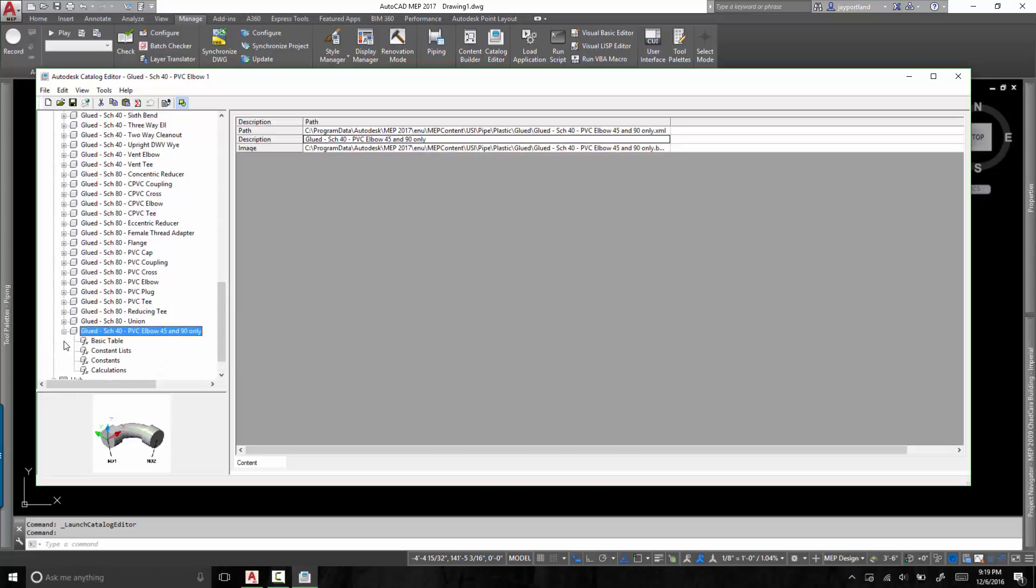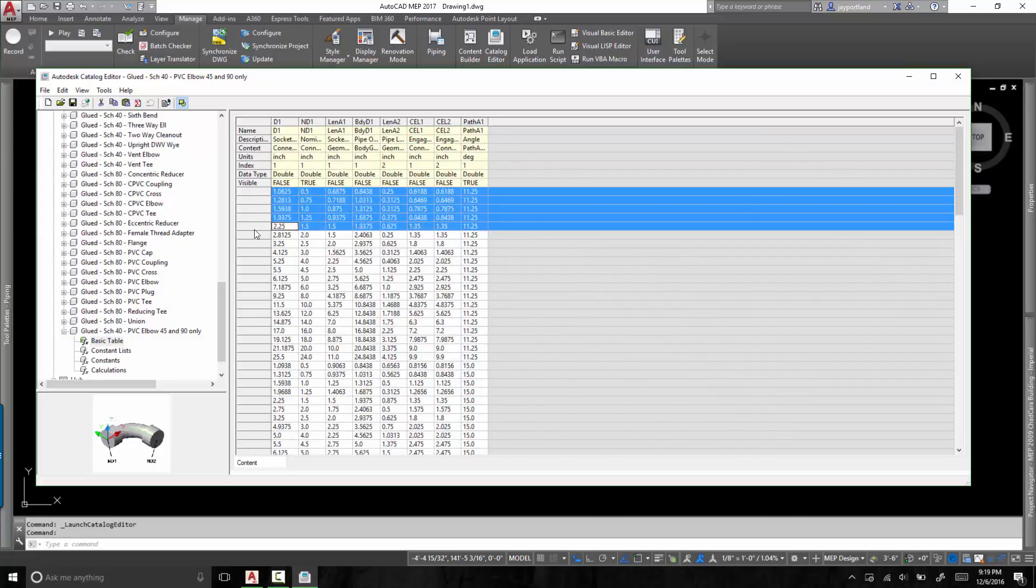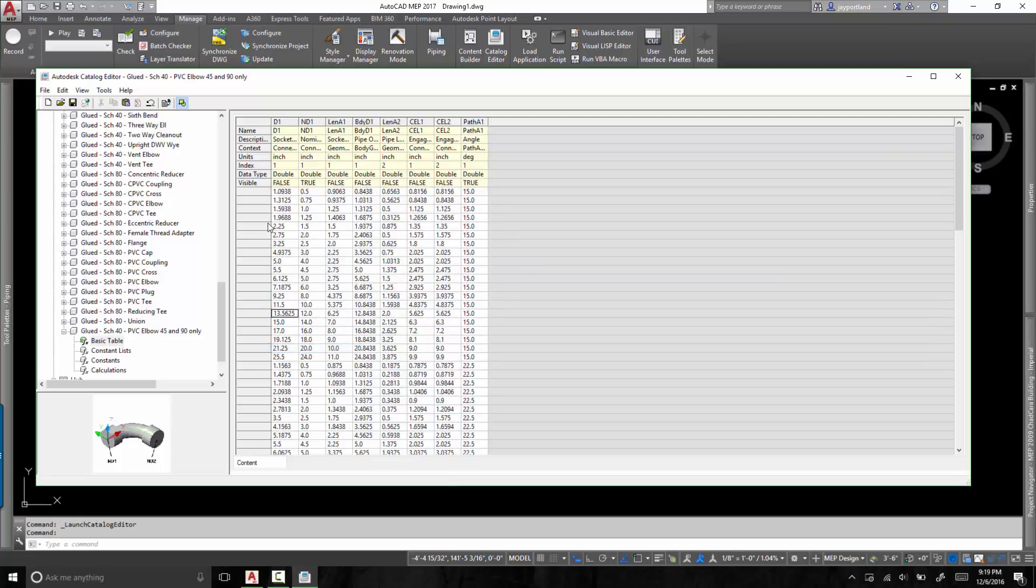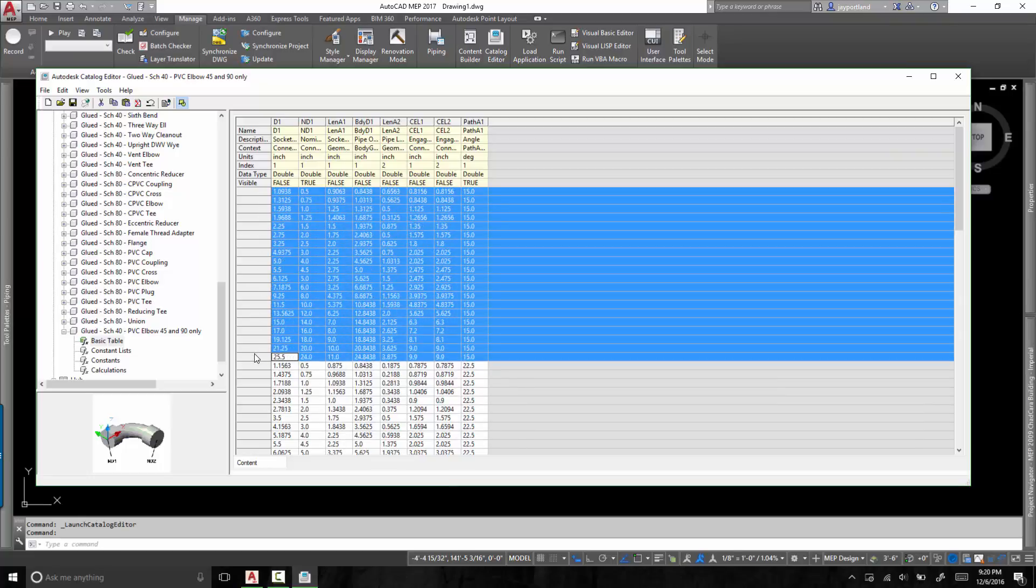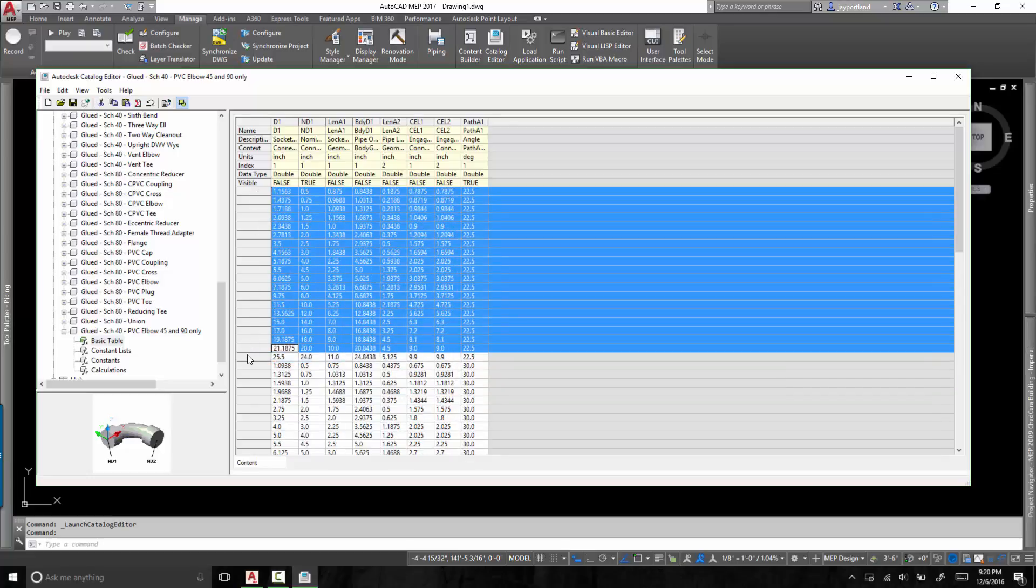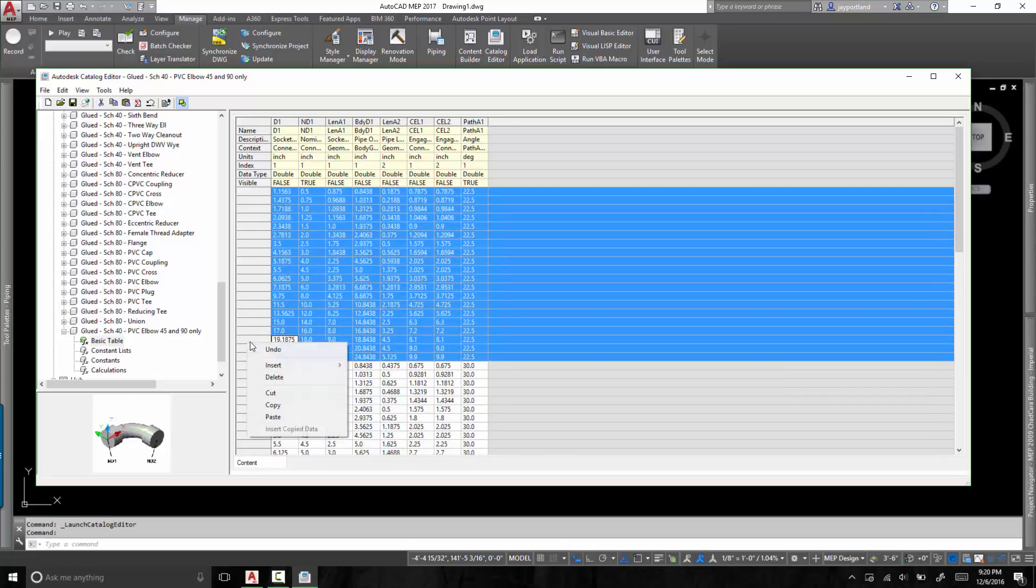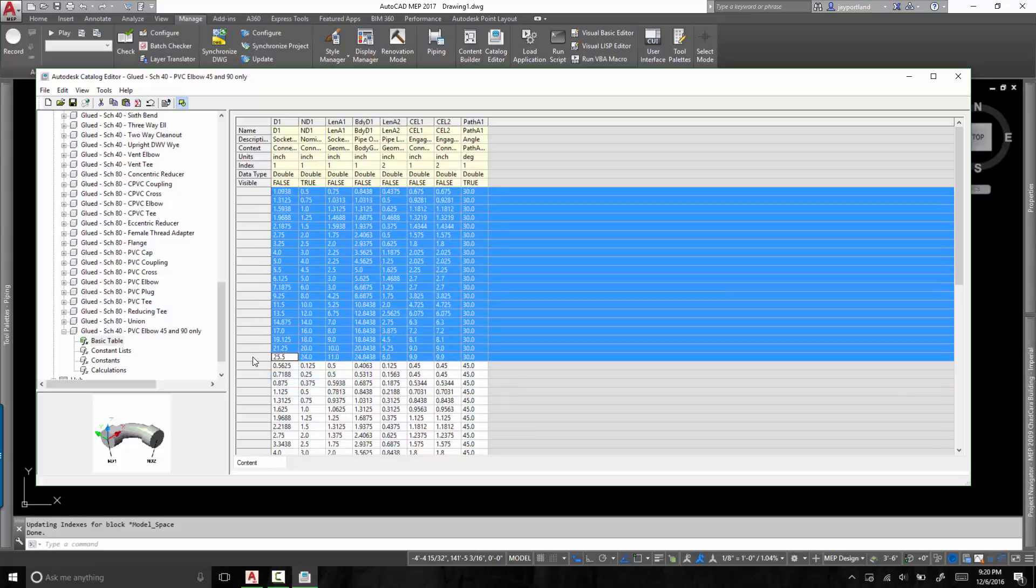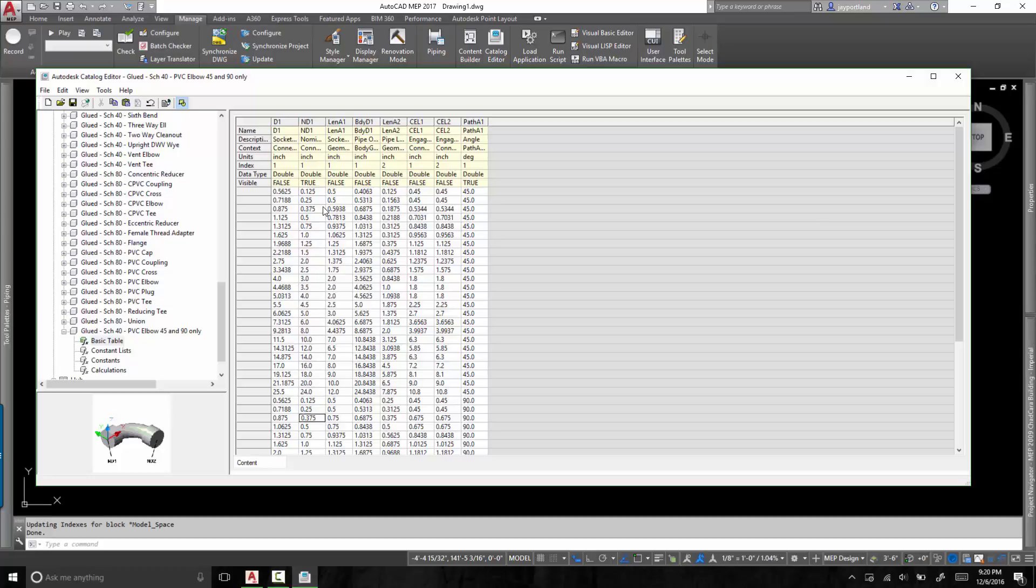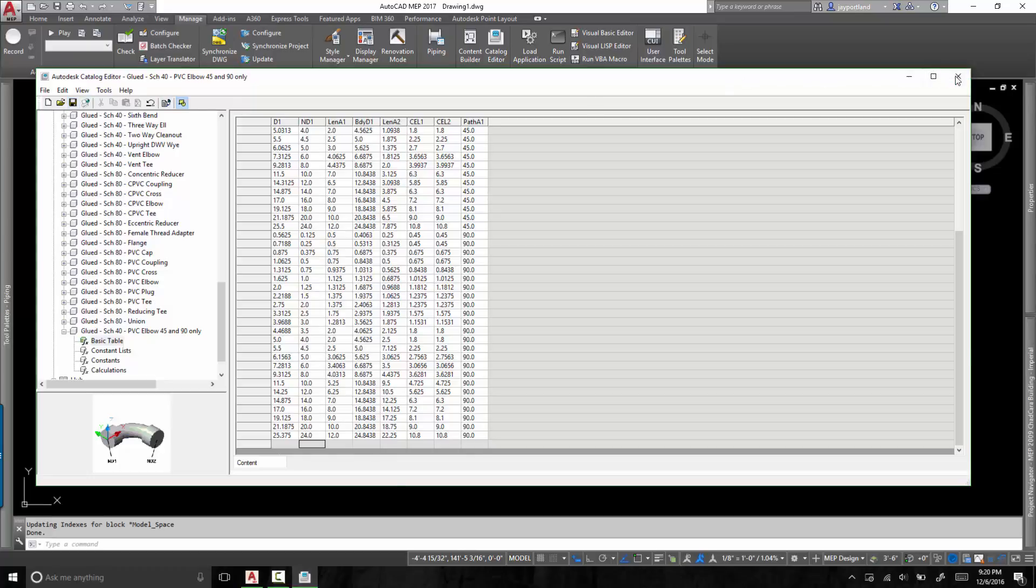All right. So now let's get into the heart and soul of modifying these. So I want to get rid of all of the 11 and a half. I don't want any of those. I don't want any of the 15s. I want to get rid of the 22 and a half. I want to get rid of the 30 degree angles. So what this leaves me with is all of these different pipe fittings in these diameters at 45 degrees as well as 90 degrees. That's all this is. So I can save this file. It's going to save my catalog file that I've just created and I can close this.